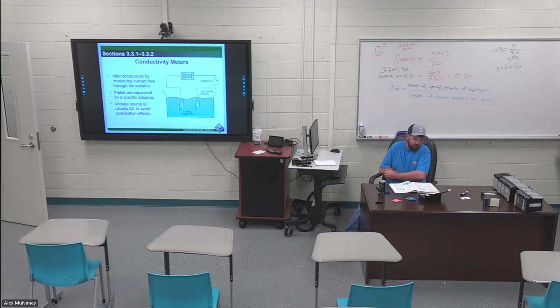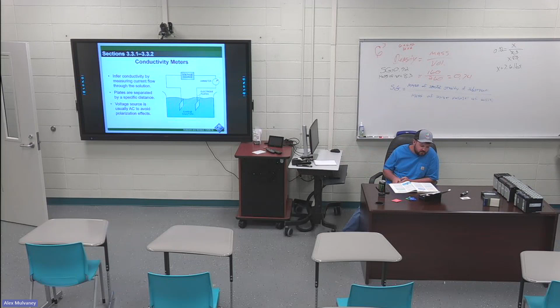Measuring conductivity. 330, the first paragraph is highlighted. A pH measurement system is designed to be sensitive to just one ion, the hydrogen ion. Similar systems can be designed to measure other specific ions. There are applications, however, where it is necessary to determine the total concentration of all ions. This can be accomplished by measuring the solution's conductivity.